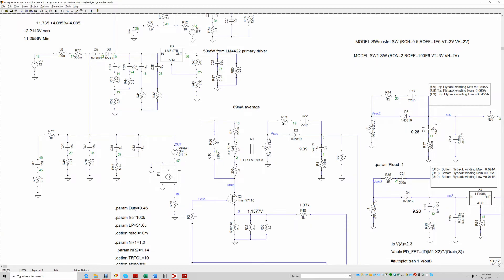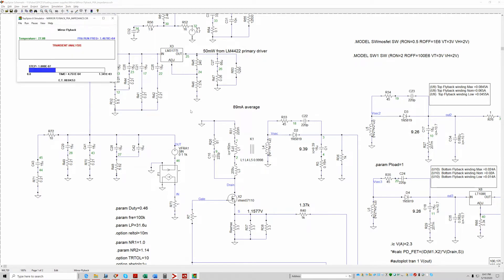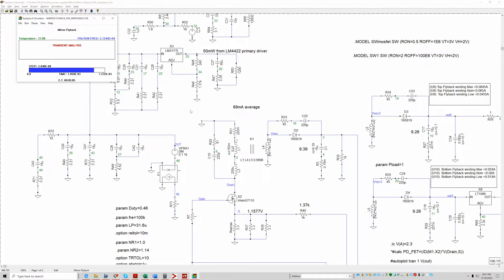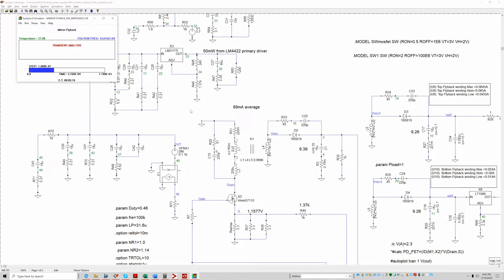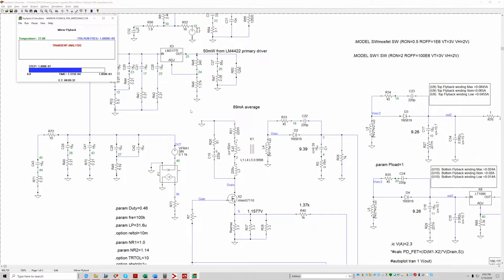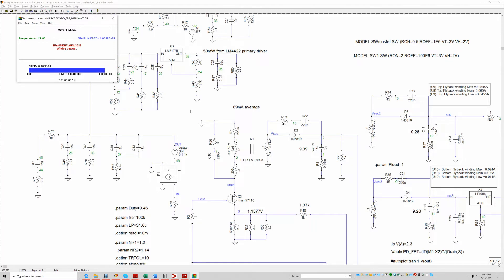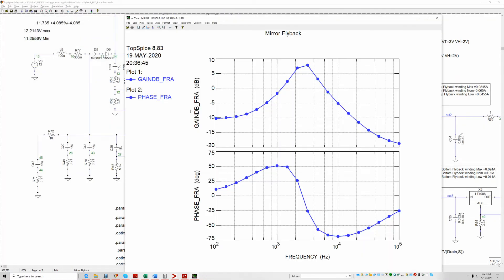So we have this set up. Since I disconnected this, this is the input to the flyback. I'm going to go ahead just for right now and ground it. Am I interested in the output impedance of the input filter? It's been close to five minutes. It's coming to the end of the simulation. Using the FRA in transient does take a little bit of time, but I believe it's well worth a simulation to run in order to check your impedances. It should stop at about 100 kilohertz.